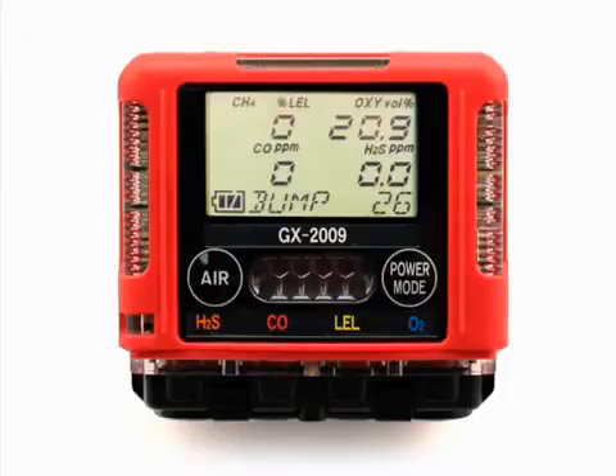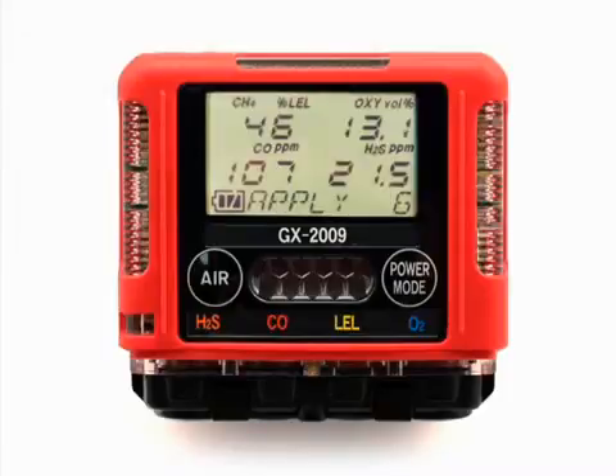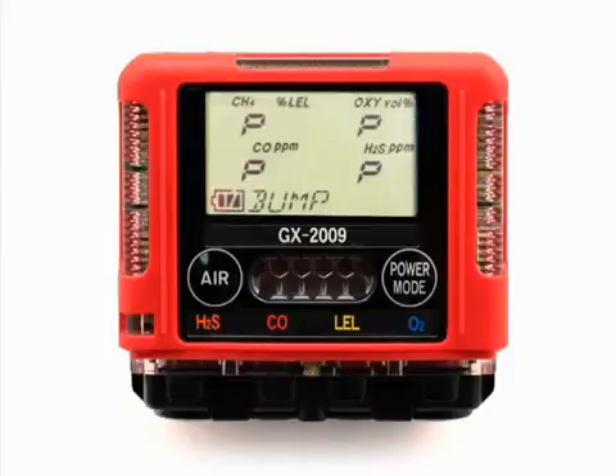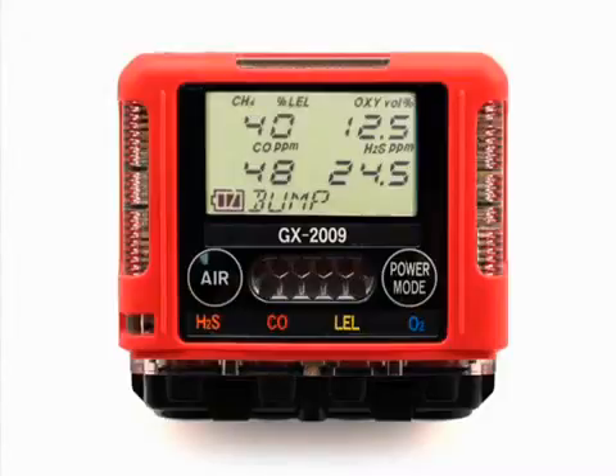The LCD will display the current gas readings and the instrument will count down from 30. Turn the regulator on-off knob counterclockwise to open it. Calibration gas will begin to flow. Do not delay opening the regulator. When calibration after bump test failed is set to off, the instrument will display which channels passed or failed the bump test. To view the bump test gas readings, press the air button. To return to the bump screen in calibration mode, press the power mode button. Turn the regulator on-off knob clockwise to close it.